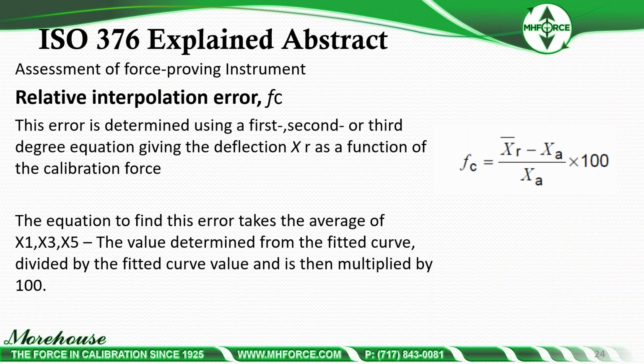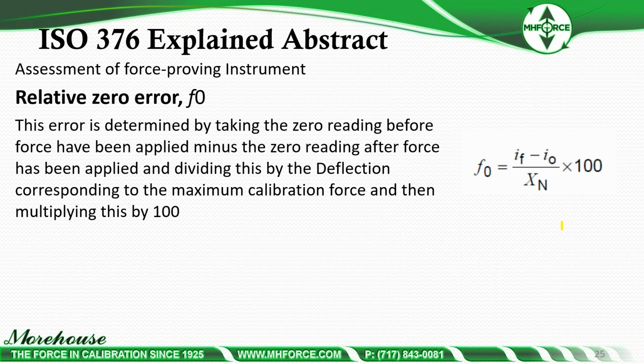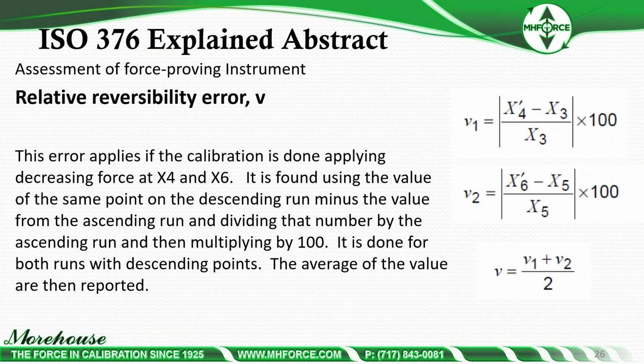Then we have interpolation error. This error is determined using a first, second, or third degree equation, given the deflection XR as a function of the calibration force. That's how you calculate that. Relative zero error. The error is determined by taking the zero reading before forces have been applied minus the zero reading after force has been applied, and dividing by the deflection corresponding to the maximum calibration force, and then multiplying this by 100. Then you have reversibility error.